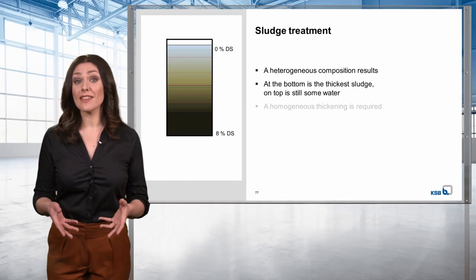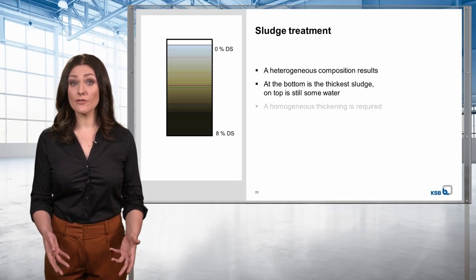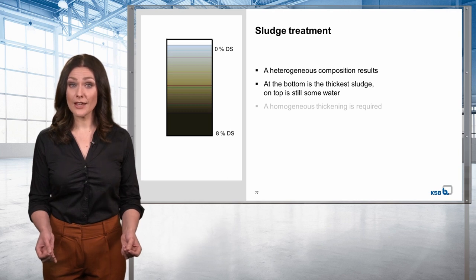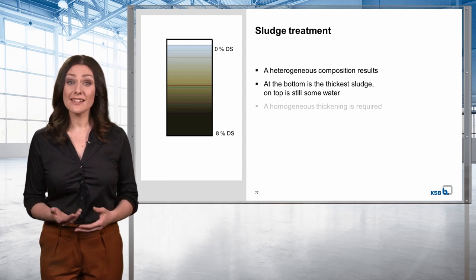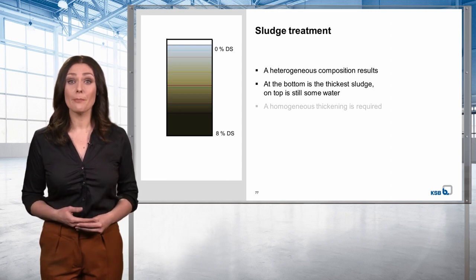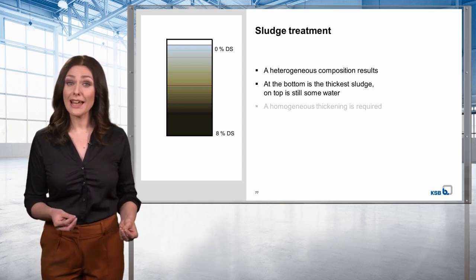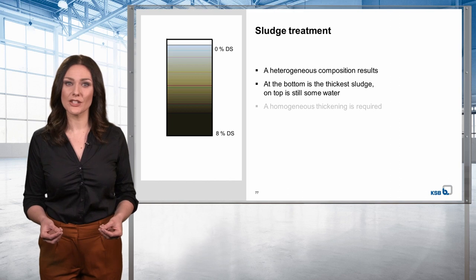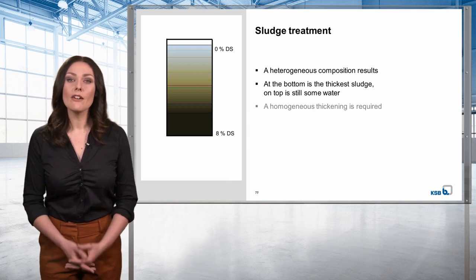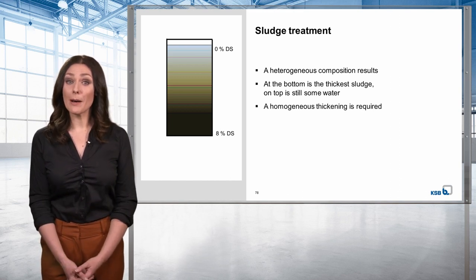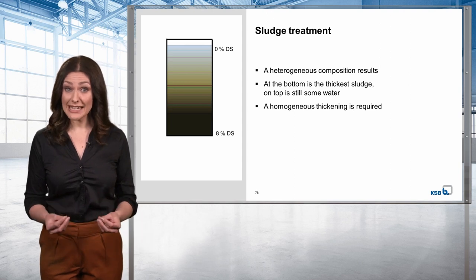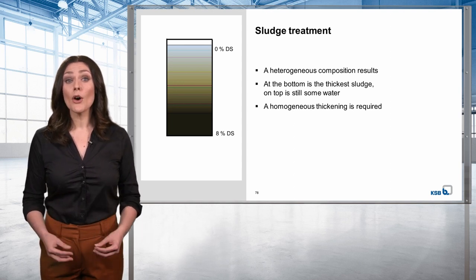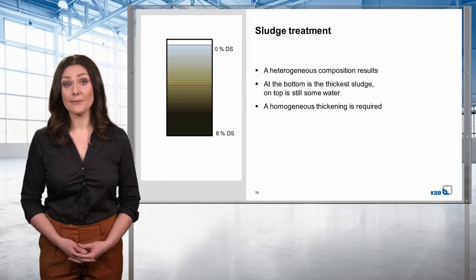The resulting thickened sludge is of a heterogeneous composition, as shown here. At the bottom is the thickest sludge from the first thickening phase; right on top, you can still see some of the water in the tank. The DS content might be 8% at the bottom and 0% at the top, for example. For the mass to be pumped off and for a uniform quality to be guaranteed for the following processes, homogeneous thickening is required.